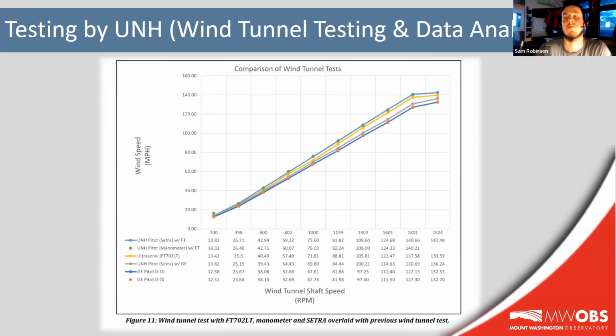It's kind of odd that the maximum speed measured by the wind tunnel reference pitot was actually about 10 miles per hour higher in the test with our FT Tech ultrasonic compared to the test with our pitot 22. And this is at the exact same RPM setting for the blower in the wind tunnel. A collective theory was that the physical size of the anemometers in the wind tunnel may have played a role here, as the body of pitot 22 is much larger than the size of the FT Tech. It's also pretty clear that the difference in wind speed between instruments across the board increases as that wind speed increased. At lower speeds, all of the instruments read relatively close to one another.